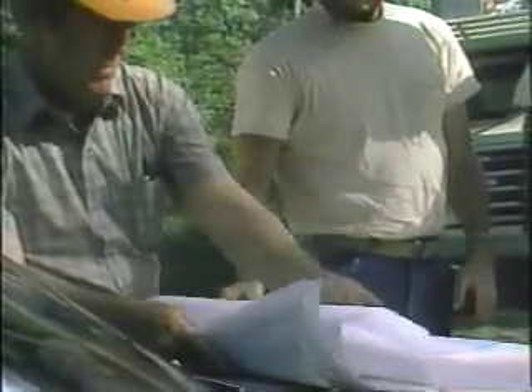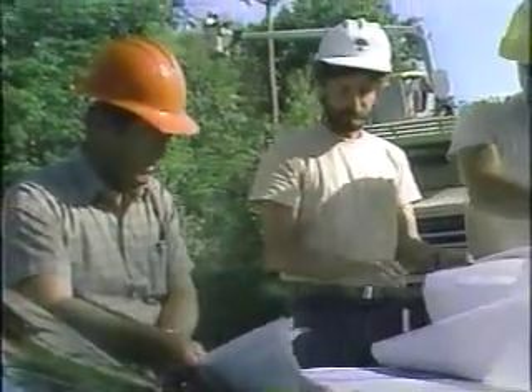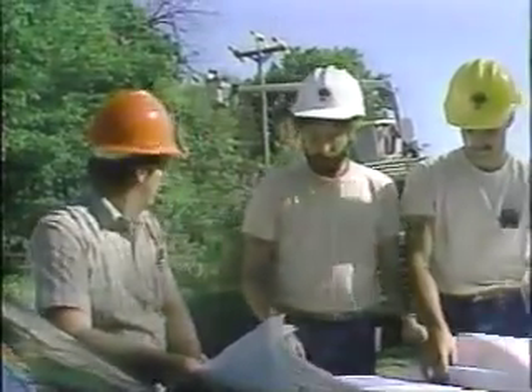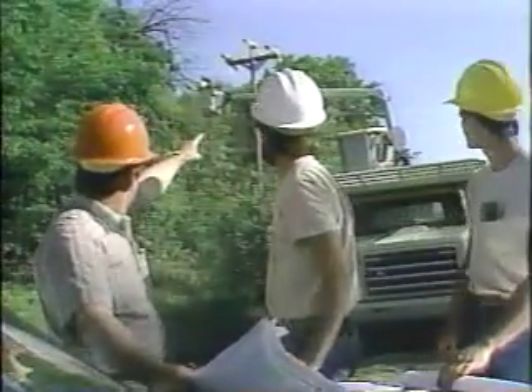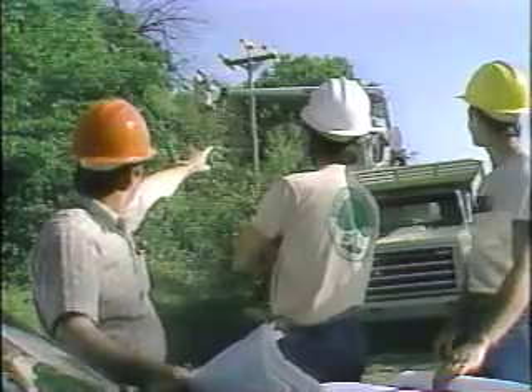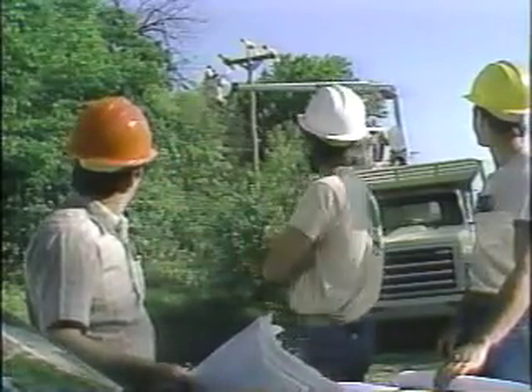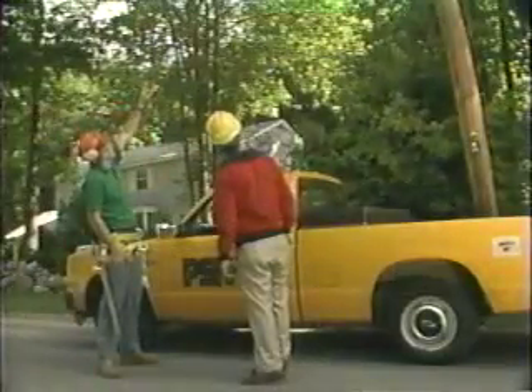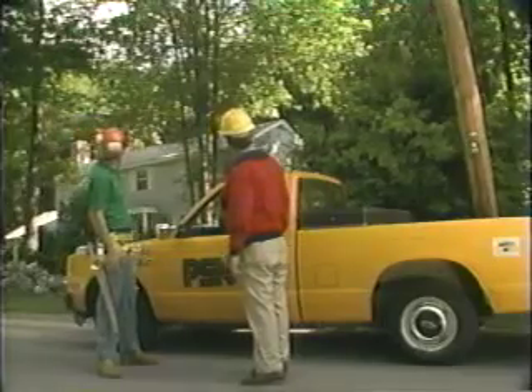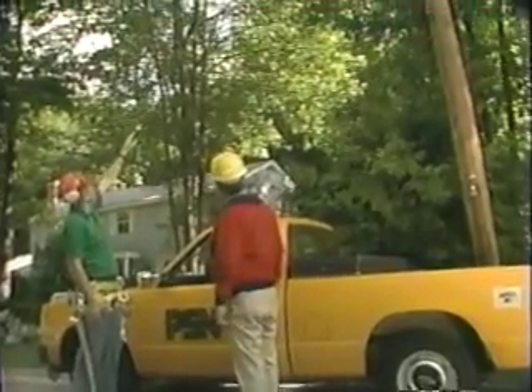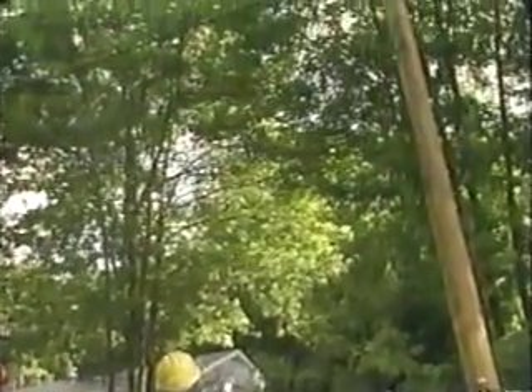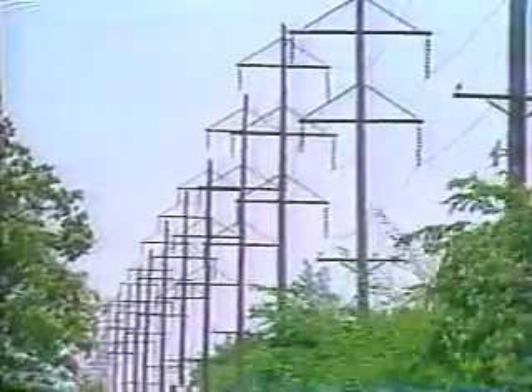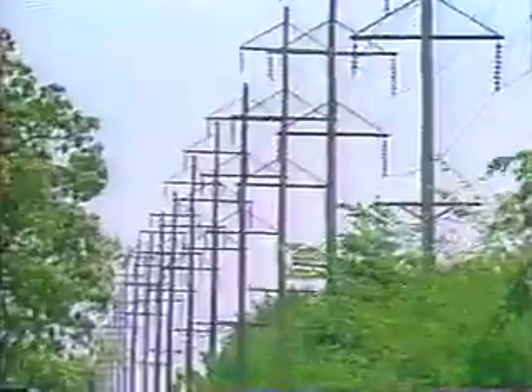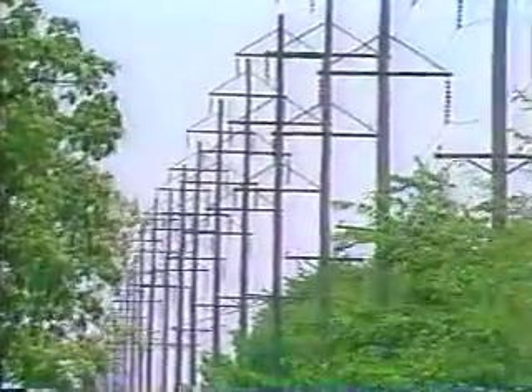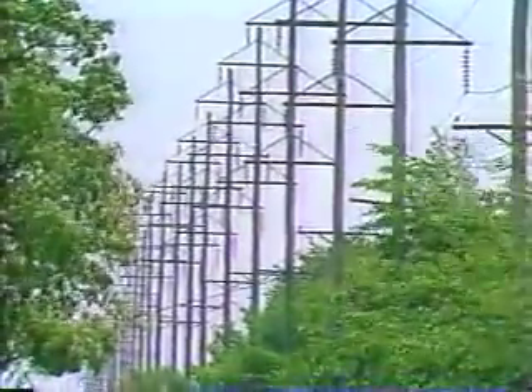Only the utility company can tell you the exact voltage in a system on a given day. You must be aware of the maximum nominal voltage of a system because of the greater ability of higher voltages to overcome a given resistance. This will govern how close you can actually come to an energized line. Key indicators, however, are the size and number of insulators. Remember, the higher the voltage, the larger and more numerous the insulators.